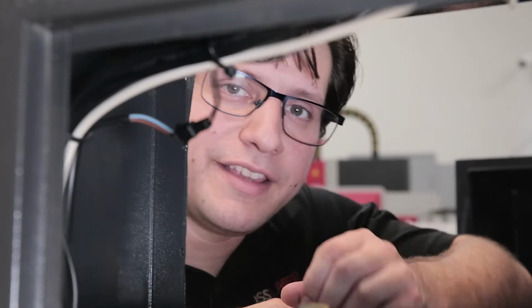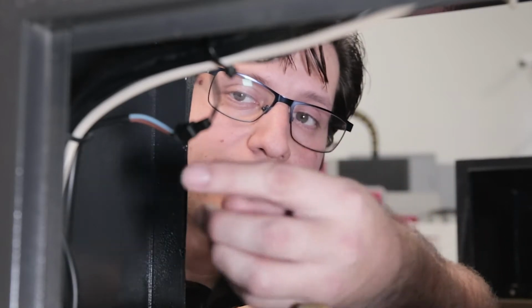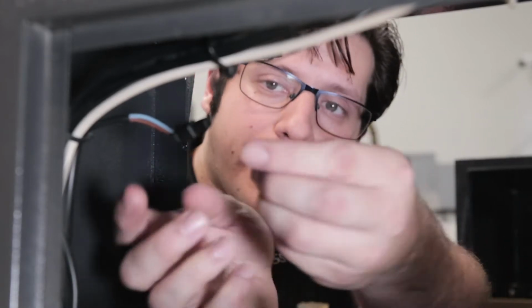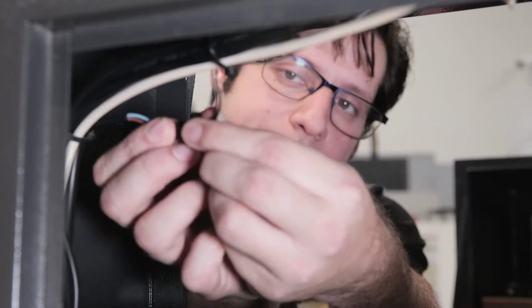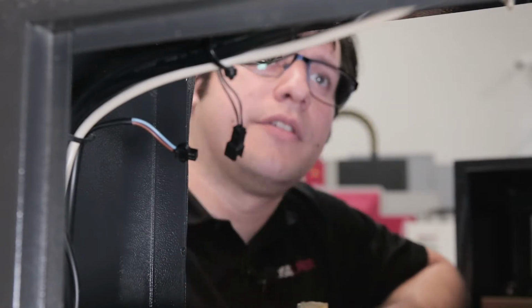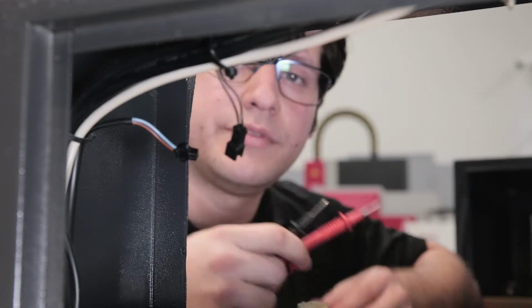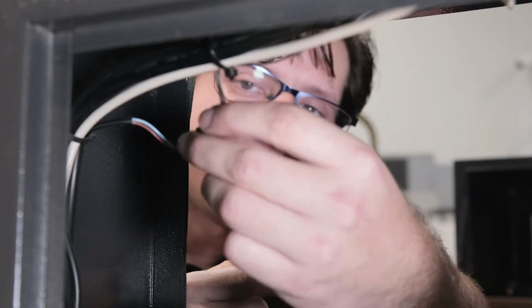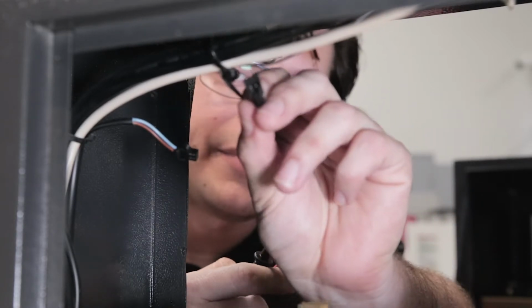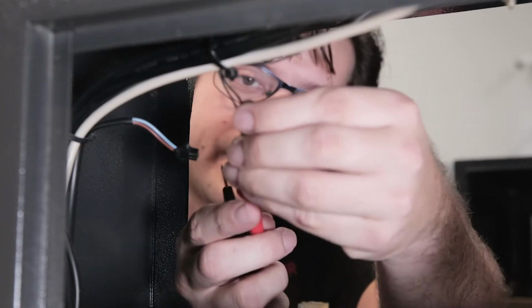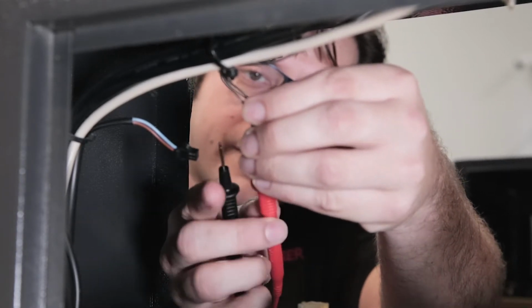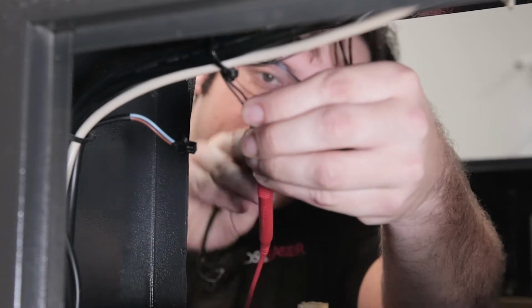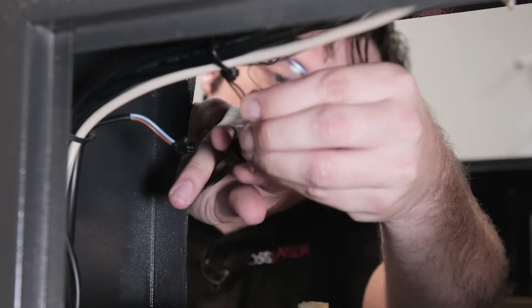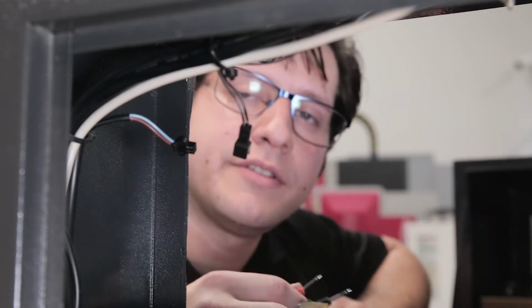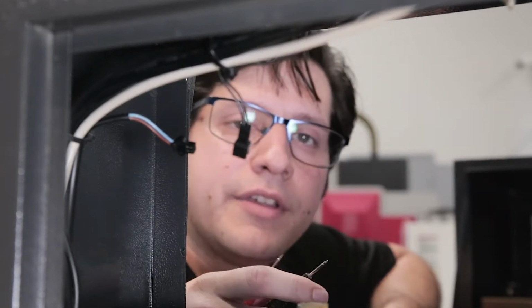So your disconnect for your door interlock is going to be located underneath your control panel. It's going to be right here. You can go ahead and undo it, and still have your magnet on your door interlock at the top. Checking for continuity, you go ahead and on the male side, place your prongs on both. So I did have continuity on the door interlock, so that's good.